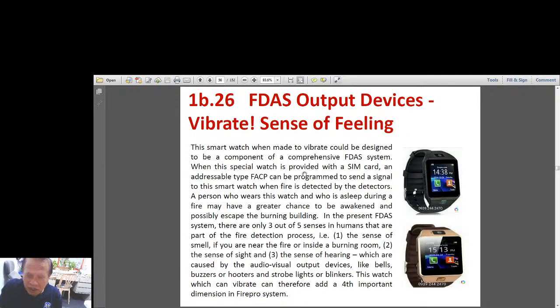and this was the one that I mentioned regarding a smartwatch system, similar to this. So this watch has a SIM card inside, and it could receive a signal from a computer or from a fire alarm and control panel that is addressable type, and it would vibrate. Of course, you can also use your smartphones because smartphones have a SIM card, so your CPU in the addressable type will also send a signal to your smartphone.